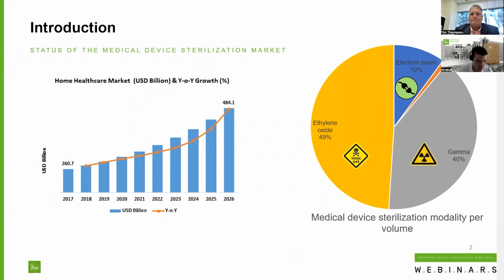of the medical device sterilization market, what we see is that the medical device market is growing and is expected to continue growing at about 7% per year. And today, the different modalities available for the industry to make sure that those products are sterilized is mainly ethylene oxide, which is a toxic gas which kills the bacteria and every kind of contamination that you might have on your products. Gamma rays, which are made with cobalt-60, a radioactive material.